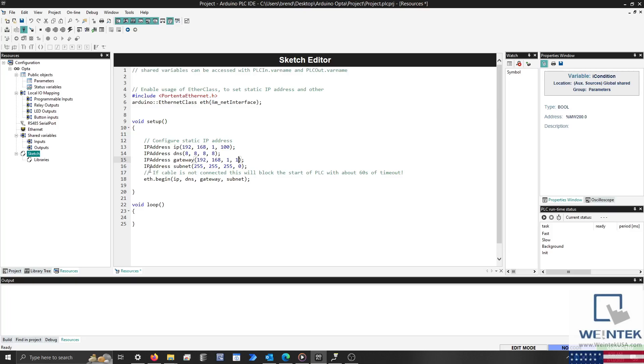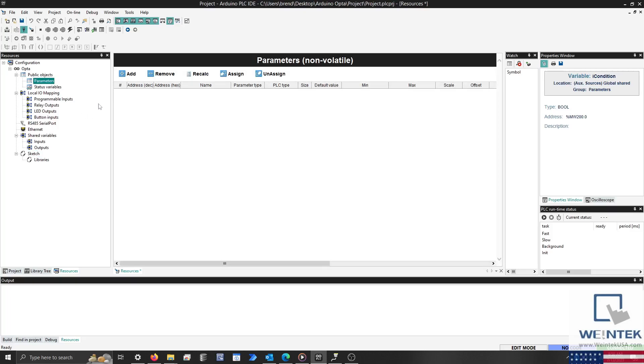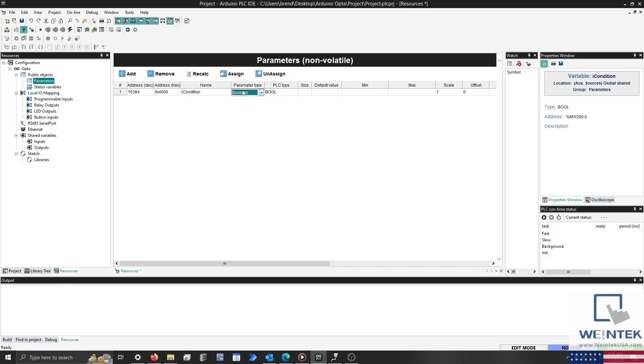Finally, select the Parameters tab to add a Modbus address. I'll name the variable assigned to this address iCondition. Set the Parameter Type to signed 16-bit and the PLC Type to bool.